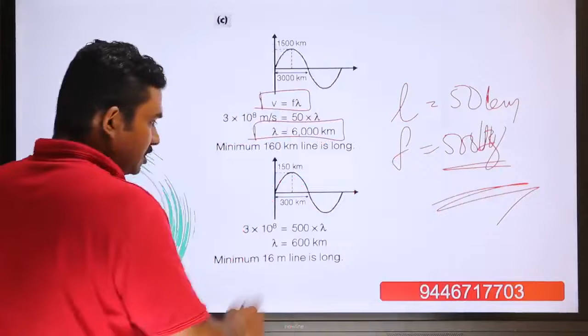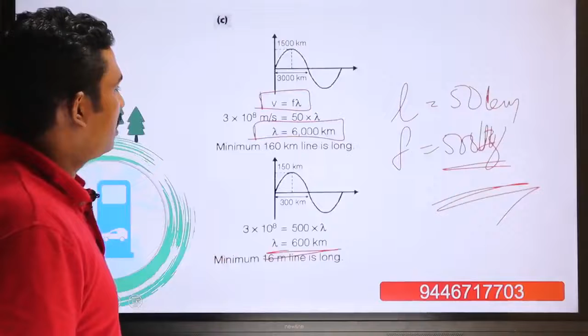So if the minimum line is 160 kilometers, here it is 16 meters line is long, is the deduction that we are getting, because here lambda is equal to 6000 and here lambda is equal to 600. So there is a difference of 10 between 6000 and 600. So what is our conclusion then? If this is the condition, then we will have to conclude the line as a long line. What is our long line condition? Our long line is a line which is above 240 kilometers.